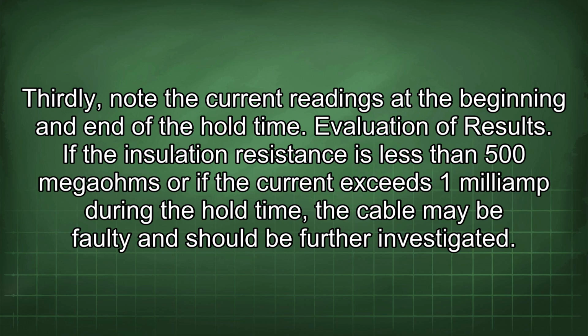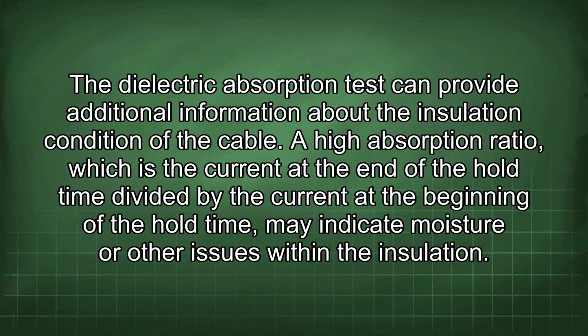Evaluation of results. If the insulation resistance is less than 500 megohms or if the current exceeds 1 mA during the hold time, the cable may be faulty and should be further investigated. The dielectric absorption test can provide additional information about the insulation condition of the cable. A high absorption ratio, which is the current at the end of the hold time divided by the current at the beginning of the hold time, may indicate moisture or other issues within the insulation.